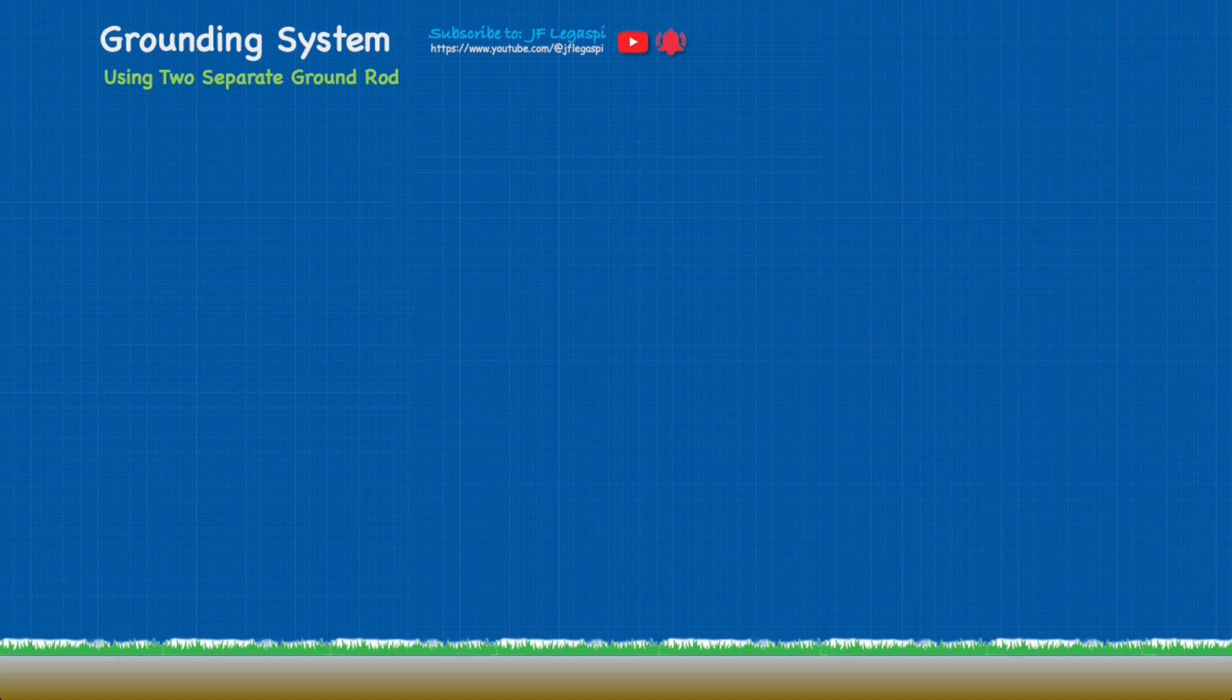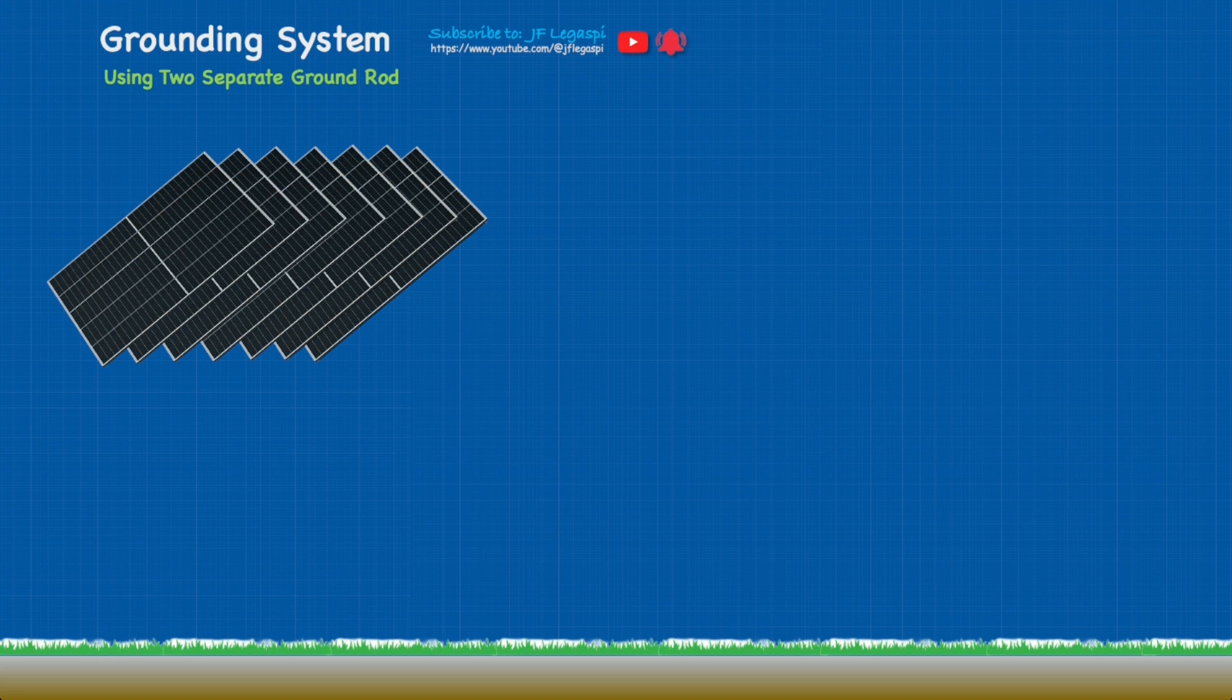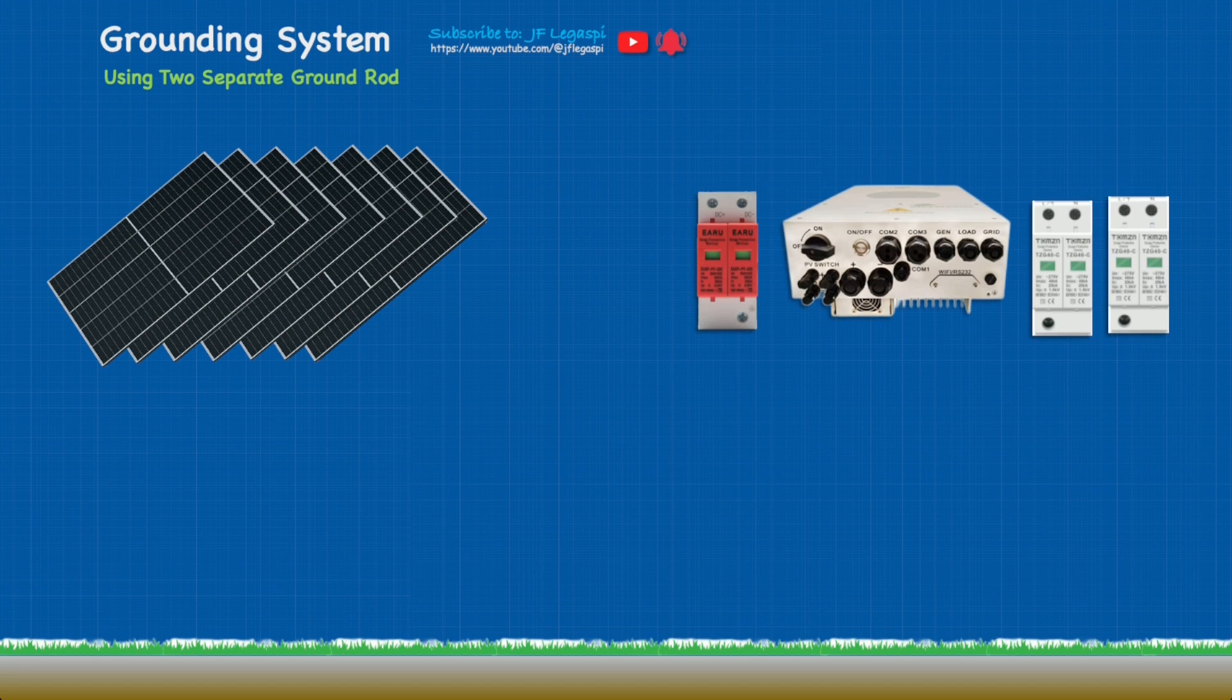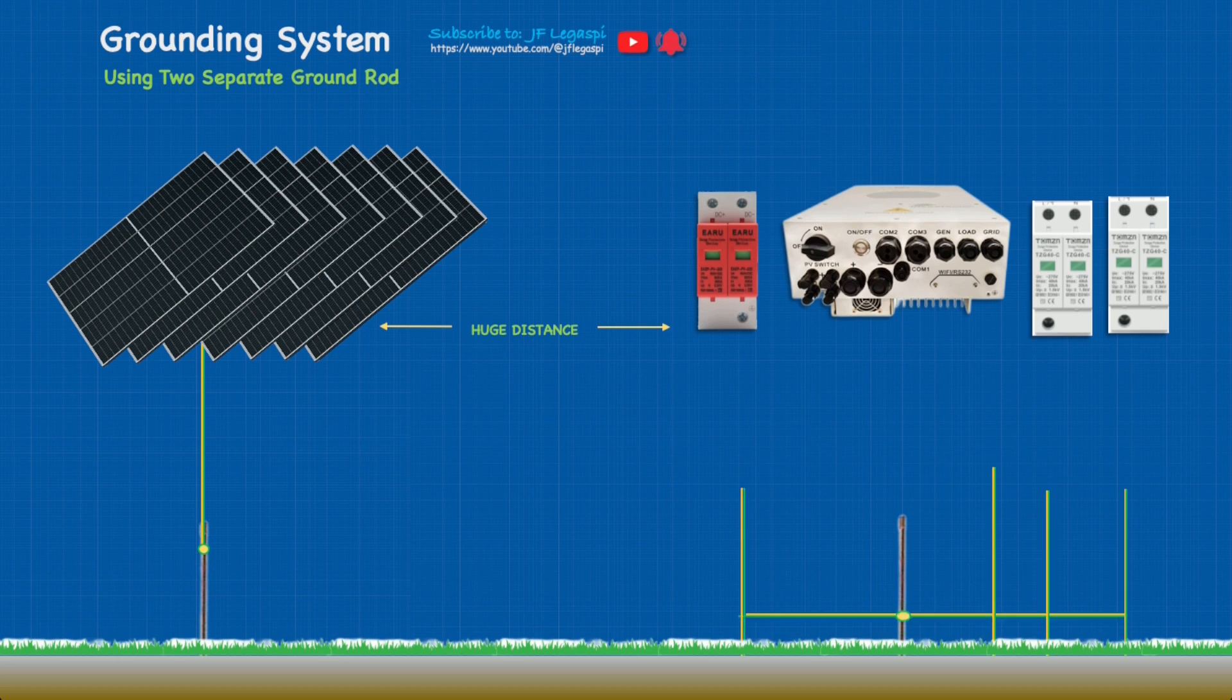Now let's take a look at using two separate ground rods. We have our PV array on this side and the main system on this side as well. If there is a huge gap between these two, huge distance, better to have a ground rod for your PV array and another one for the main system.